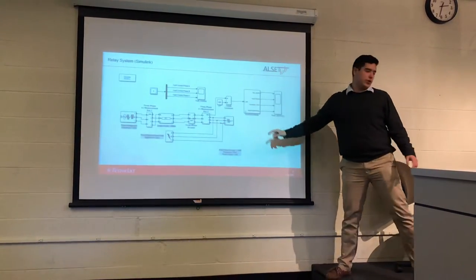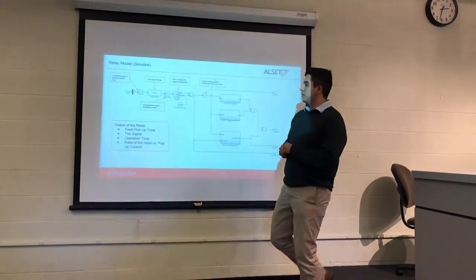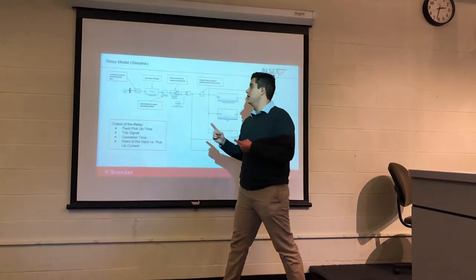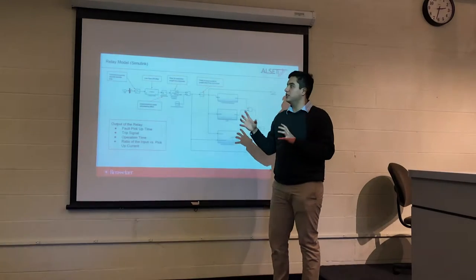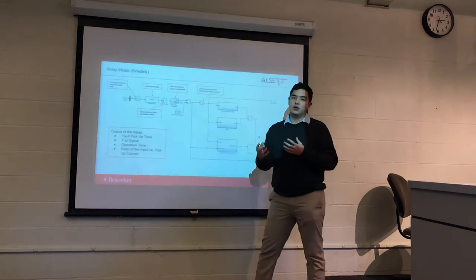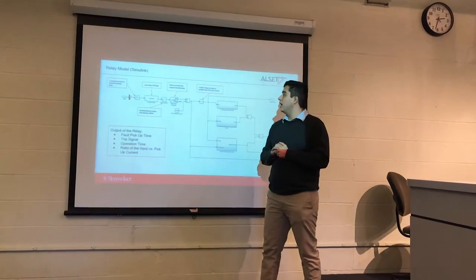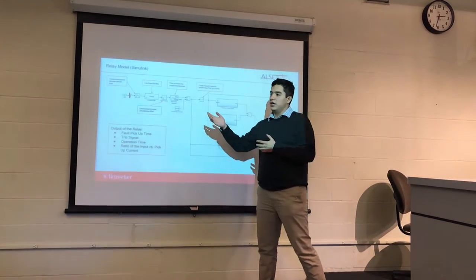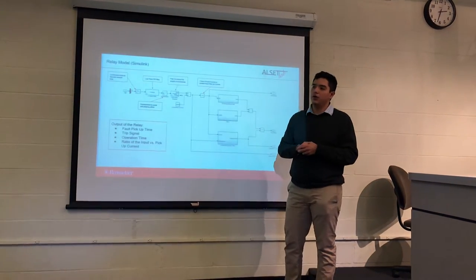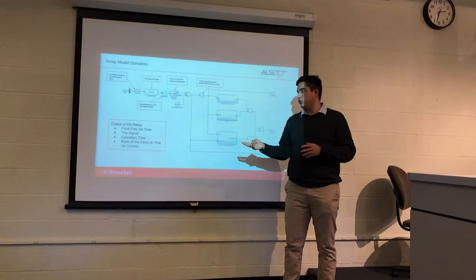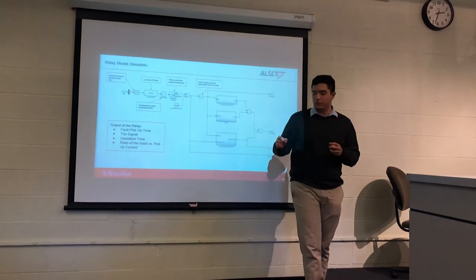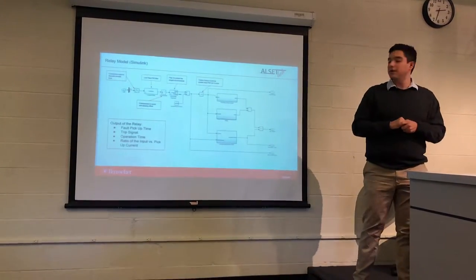So now we're looking inside of the square. The first thing we have is we would take the three phases and only take one of the phases in order to analyze it. And then we would discretize it by using a zero-order hold. We filter and down-sample in order to take away the anti-aliasing effect. And then we use a filter in order to get the signal's fundamental. We convert it into RMS and then we compare it to our fault pick-up current that is previously set in order to eventually get out of the relay the fault pick-up time, the trip signal, the operation time, and then the ratio between input and pick-up current.